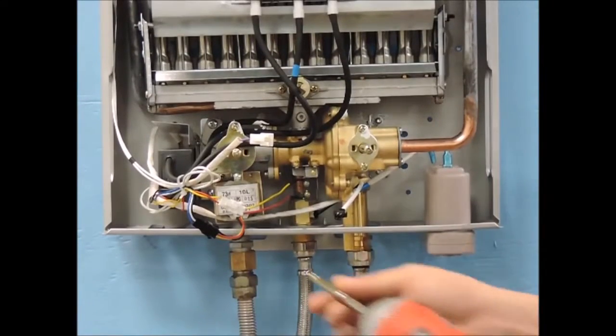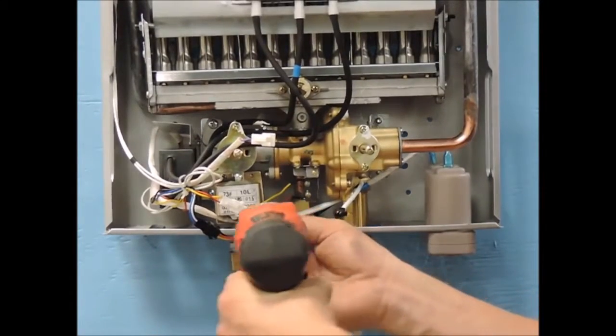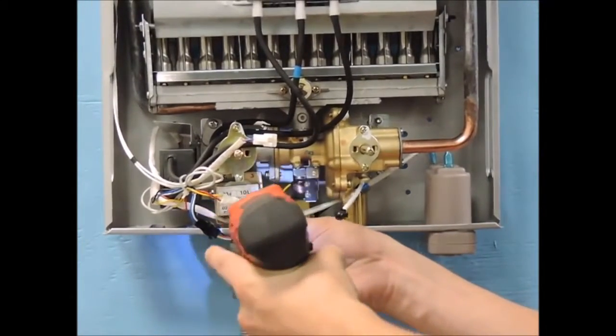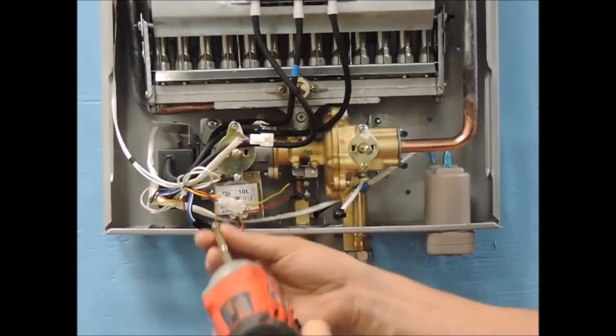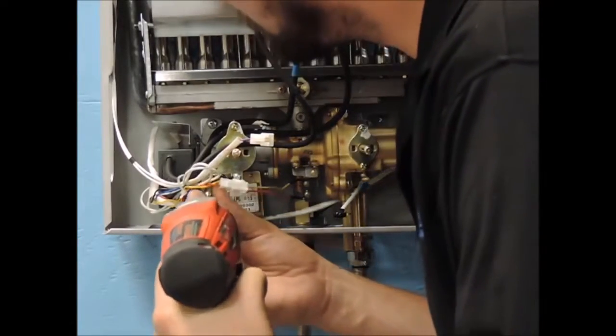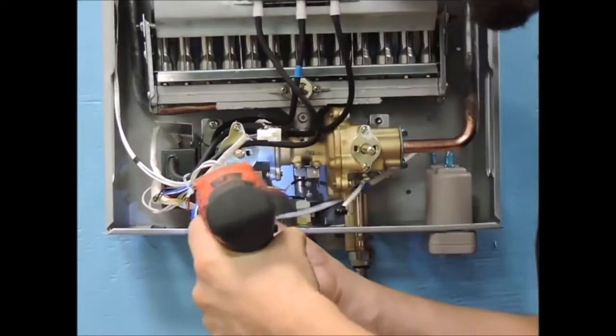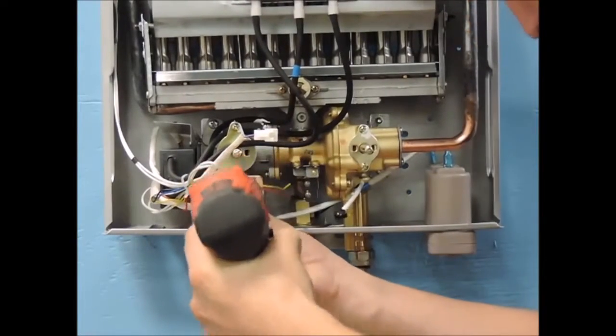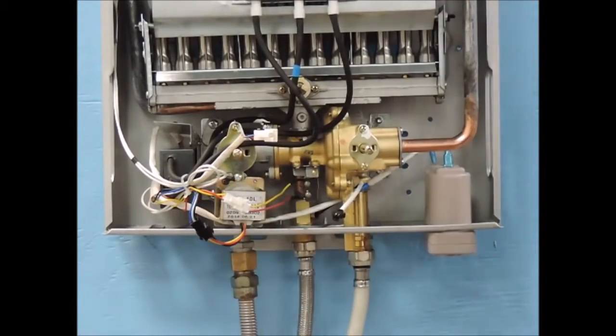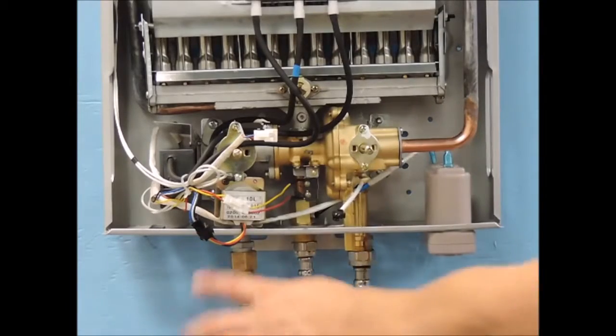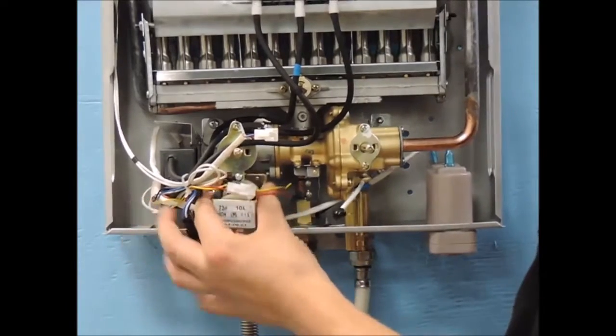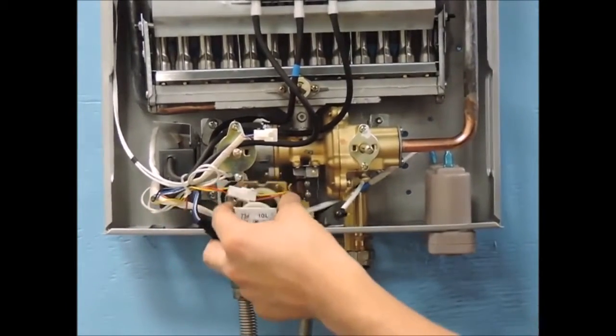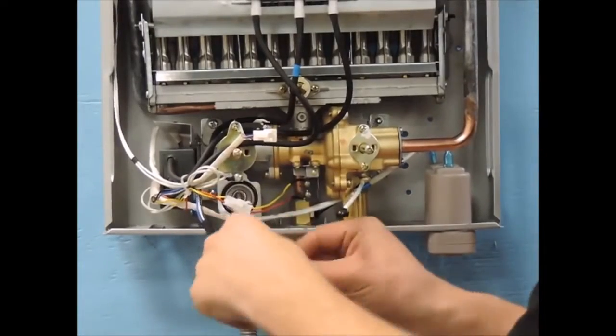Now, locate the gas solenoid. It will be located on the gas valve in the lower left-hand corner. Next, locate the micro switch. It is a small black rectangle with 2 wires coming from the left-hand side, located on the bottom side of the brass water valve, near the bottom center of the heater. Use your finger or a flathead screwdriver to lift the metal tab away from the micro switch manually.